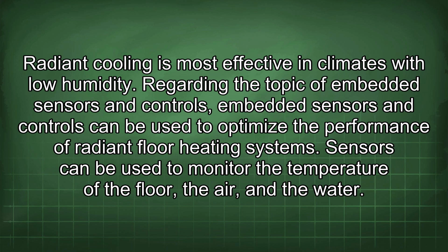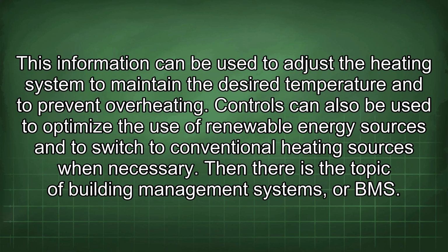Regarding the topic of embedded sensors and controls, they can be used to optimize the performance of radiant floor heating systems. Sensors can be used to monitor the temperature of the floor, the air, and the water. This information can be used to adjust the heating system to maintain the desired temperature and to prevent overheating. Controls can also be used to optimize the use of renewable energy sources and to switch to conventional heating sources when necessary.